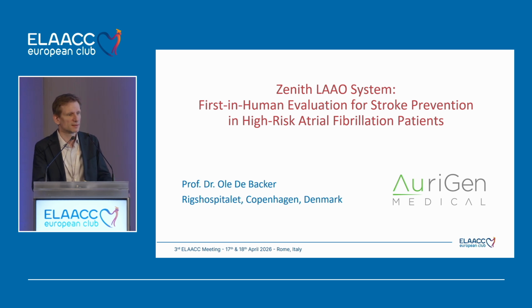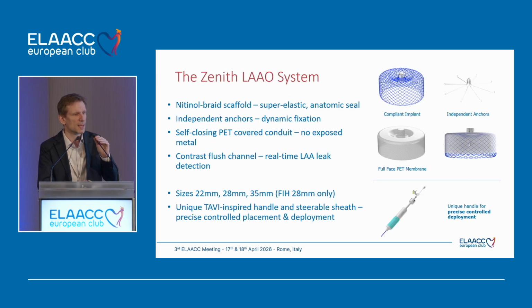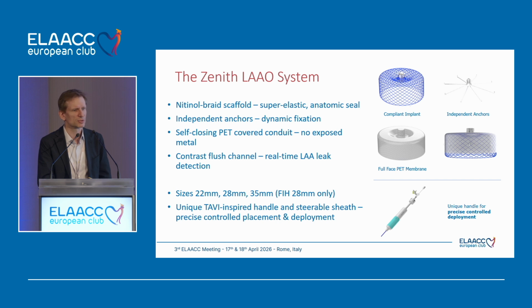So this is the Zenith LAAO system, and what is it about? It's a nitinol-braid scaffold, as you see on the top, which should be very compliant. Then it has independent anchors, which can be deployed in a second step of the procedure. You have a self-closing PET covered conduit, so there should be no exposure of metal. That's to keep the DRT rate low. And you can also do a contrast flush channel, so you can have the device in place, give contrast internally in the device, and see whether there is a leak going into the left atrium, yes or no, before the release.